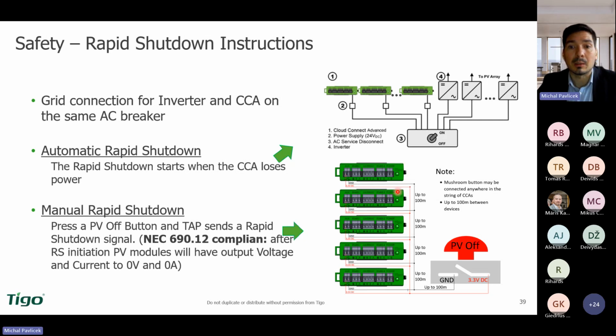It can be even better than this: you can add one additional red button to the power supply. So the firemen put down the main switch, and there is a red button to push to lose the power. Immediately everything goes to rapid shutdown. When I say immediately, the norm, and we are following the UL, which is the strongest and strictest norm, says that it must happen in 30 seconds. Now, rapid shutdown is even faster, but the 30 seconds are there because there is still a voltage in the capacitors of the inverter, which can go reverse. So for safety reasons, the norm says 30 seconds. So 2 cases, for the service and for the firemen. Everything is available.